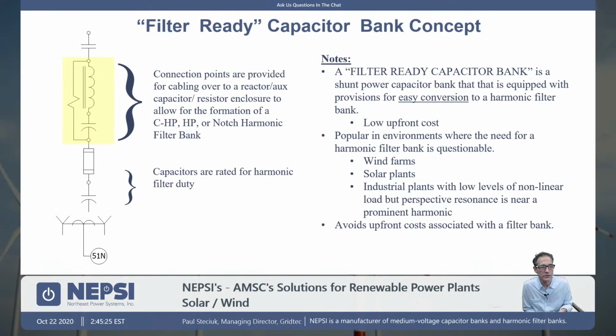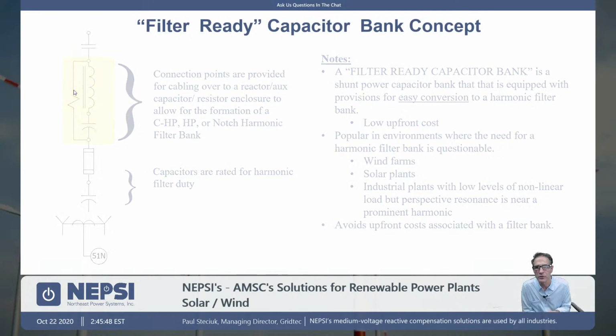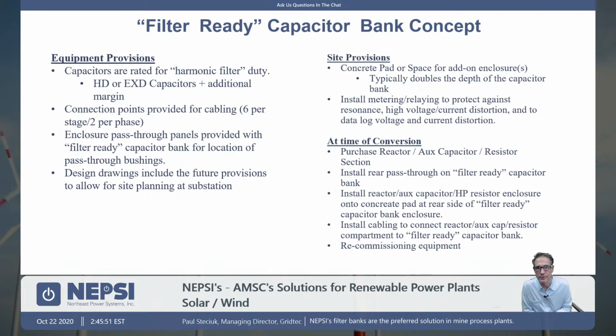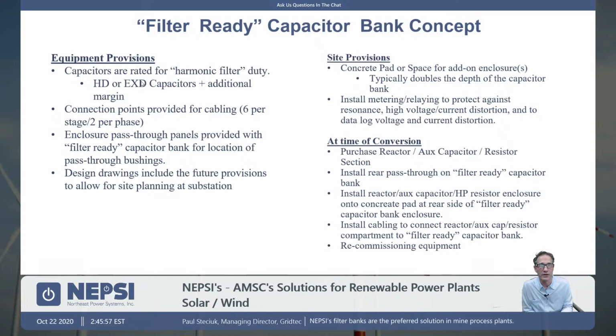So if you purchase a cap bank and you specify filter-ready, what it means is that you're going to specify higher rated capacitors, and you're going to specify the provision for it to be converted to a harmonic filter. That conversion process involves the installation of a reactor bank, a cap bank, and a resistor bank. And that's what we talk about here. You're going to buy HD or EXD capacitors if it's an Eaton capacitor. Typically at 34.5 kV, the line to neutral voltage is 19.9.